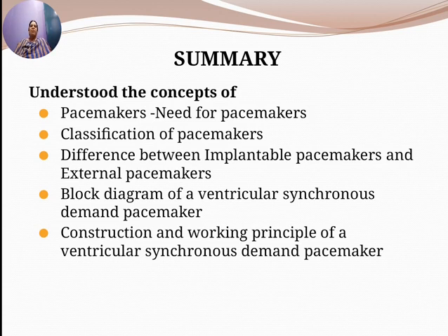The operation of the ventricular inhibited or ventricular synchronous demand pacemaker: the sensing electrode picks up the R wave. The refractory circuit provides a period of time following an output pulse or a sensed R wave, during which the amplifier in the sensing circuit will not respond to outside signals. The sensing circuit detects the R wave and resets the oscillator.